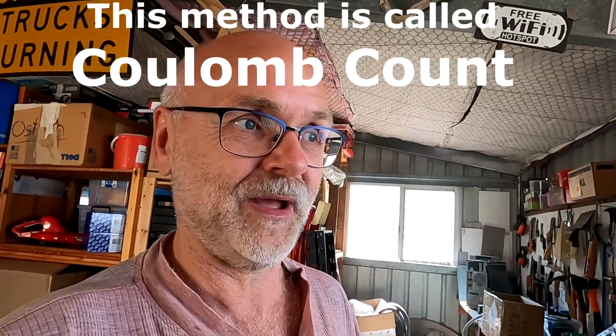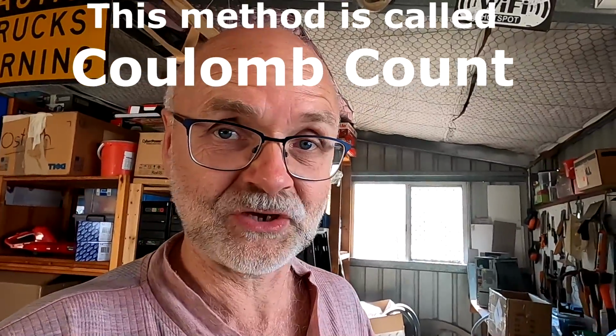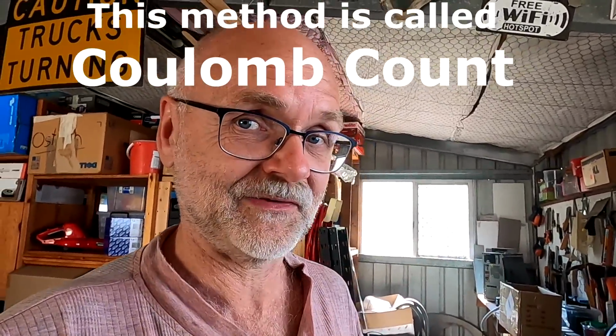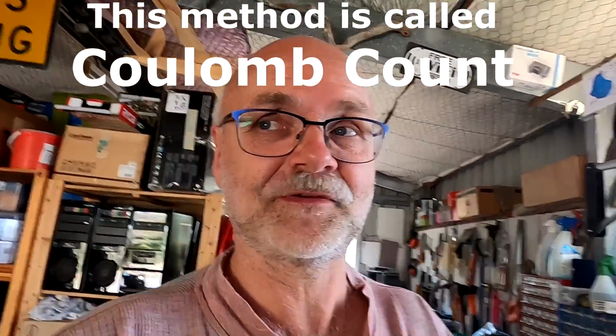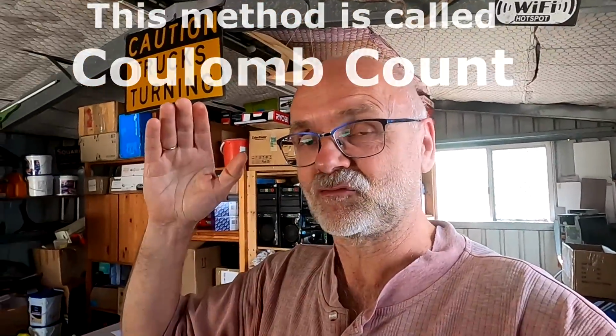So the only measurement we have is the capacity, the ampere hours going out of the battery. This is something the smart shunt does, and also your BMS. It counts the ampere hours. As soon as you fully charge, it resets its reading to 100%, then counts the ampere hours going out when you discharge, and going in when you charge from solar or the grid, calculating the state of charge. This is actually the most accurate calculation you can do to determine the state of charge of a battery.